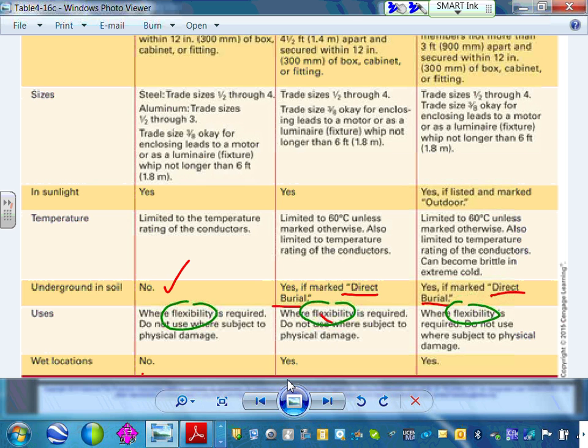Now, in wet locations, can you use this? If you go through New York or any states that don't use the 2014 code, they used to allow it, guys. I think they stopped around 2005, maybe 2002 - they used to allow this outdoor. So there are certain states that still allow it outdoor, but I would say no outdoor for this guy. These are non-metallic or have a jacket on them because they want to use them in wet locations.